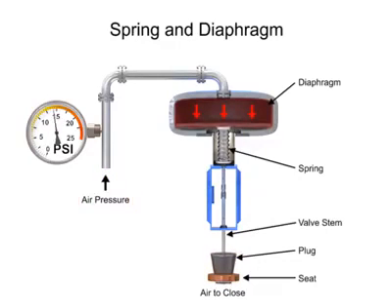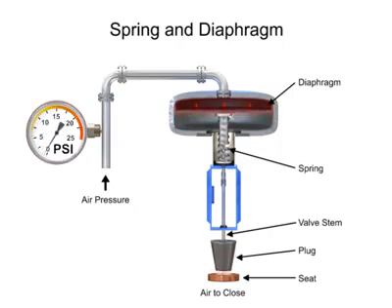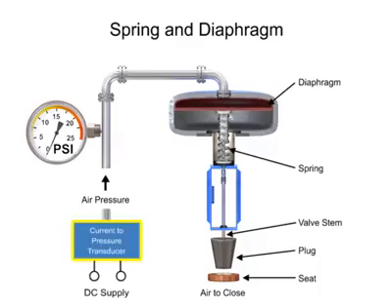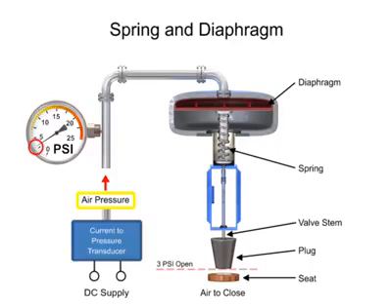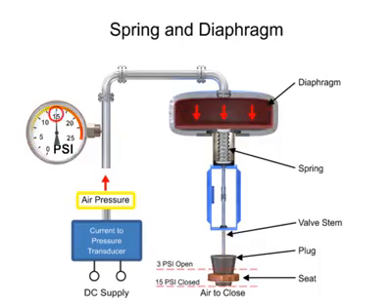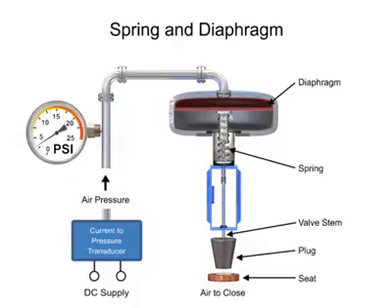With no air pressure, the restrictor is pushed upward by the spring to act as a normally open control valve. To vary the position of the restrictor and flow through the valve, a current to pressure transducer can be used to provide a 3 to 15 psi signal to the diaphragm. At 3 psi the valve is maintained open, and at 15 psi the valve is maintained closed. Pressures between the 3 to 15 psi range proportionally change the flow of the valve.